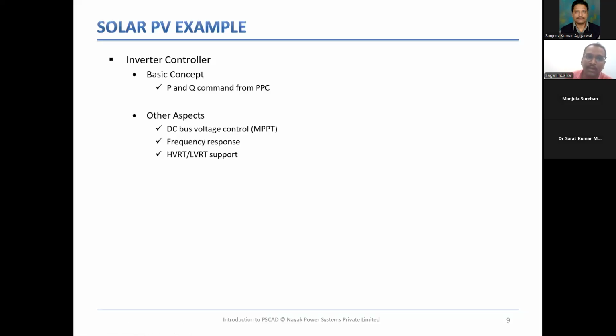Other components of a plant are your inverter controller. As I said, it will follow the P and Q command from the power plant controller. Along with generating P and Q, it also performs other functions, for example DC bus voltage control. It also performs frequency response, I will come back to that point again, and it also provides LVRT, HVRT support.